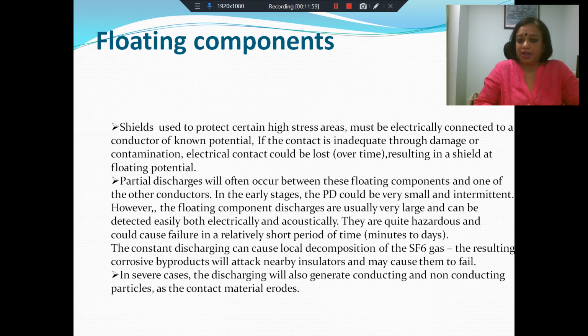But what can happen is that over a long period of time, the contact can wear off. There might be damage to the contact, there might be contamination, and as a result, over time, the electrical contact with any of the fixed potential surfaces might be lost. So then you have a shield which is neither earthed nor held at a particular potential, so it will acquire whatever potential according to its geometrical configuration. And so you have a shield which is at a floating potential.